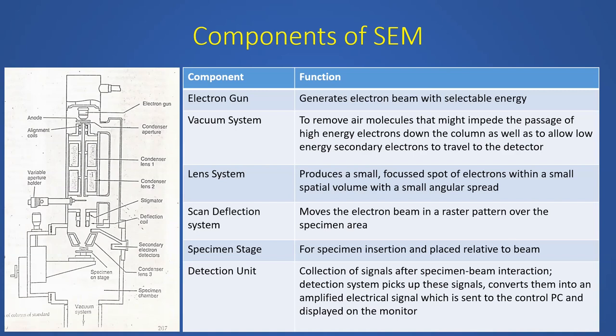That's good enough. Basically you work at lower kVs for best results in biological SEMs, because we are only concerned with the surface features. We don't want signals coming from deep within the sample. We are concerned about the secondary electron signals. So that's why we don't have high kV SEMs, unlike TEMs.